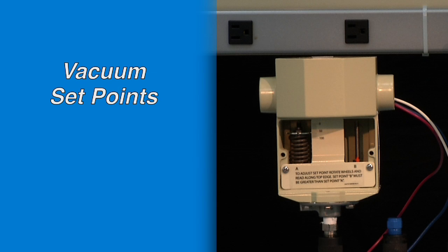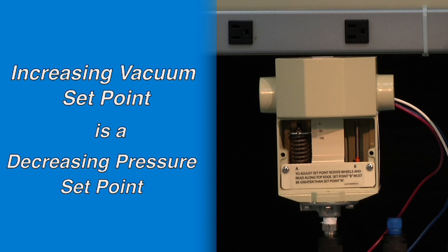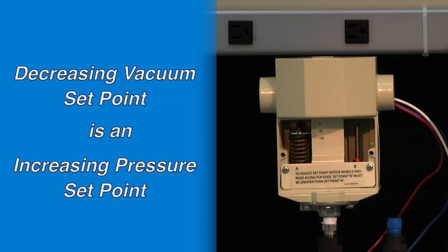For set points on vacuum range switches, it is best to think of the set point as a negative pressure. So an increasing vacuum set point is a decreasing pressure set point and a decreasing vacuum set point is an increasing pressure set point.